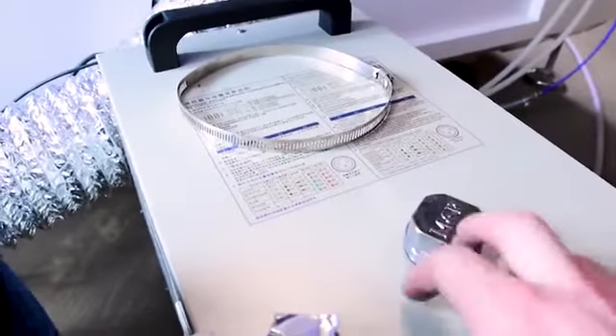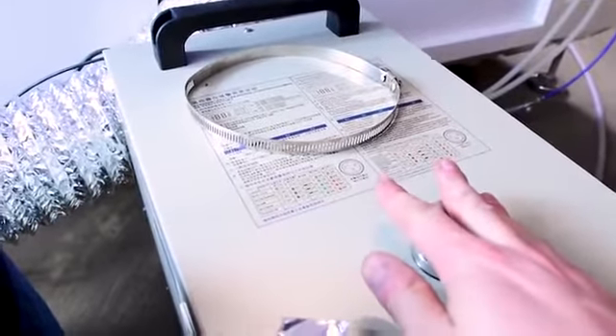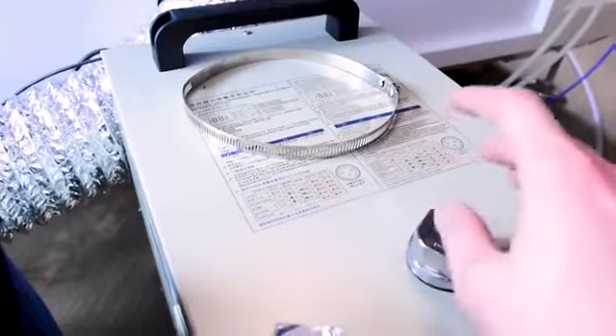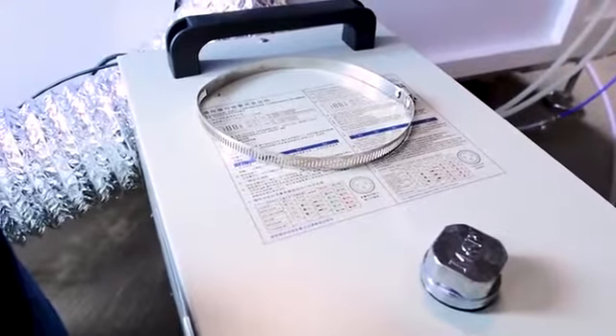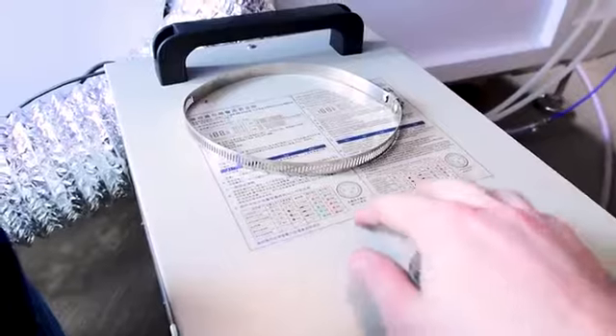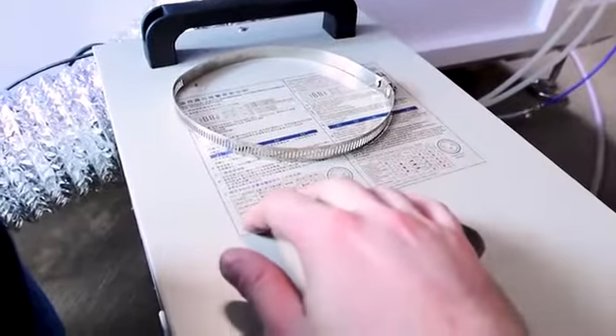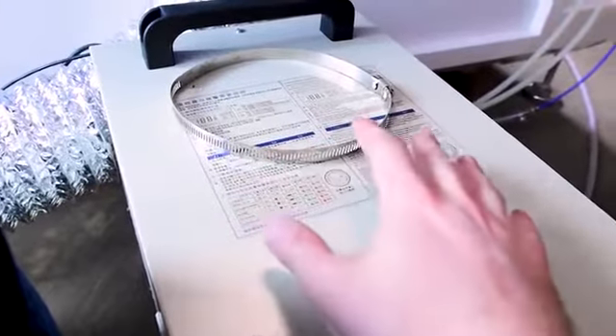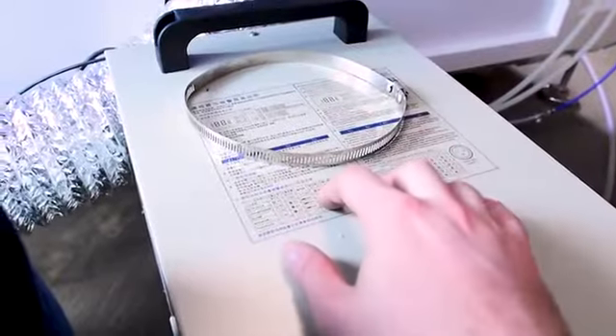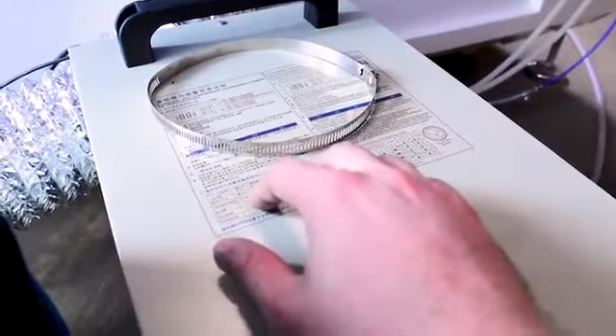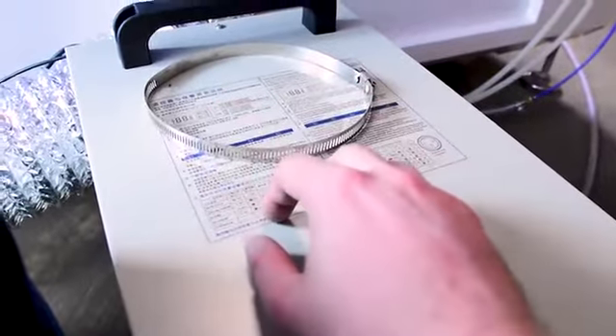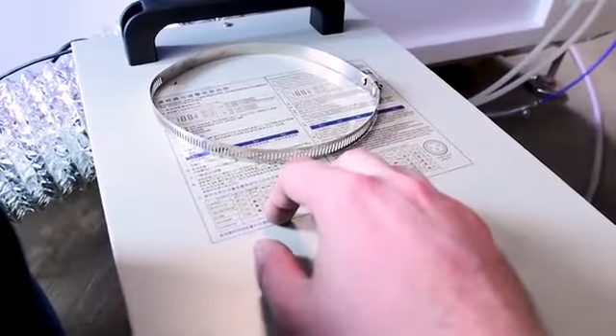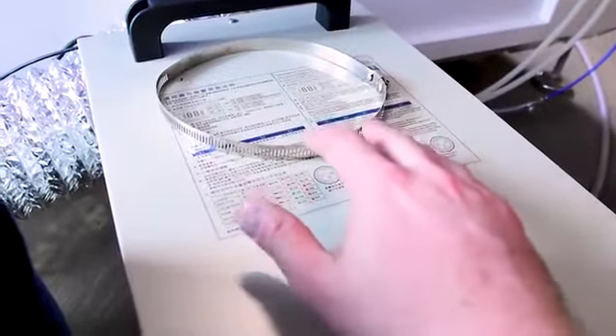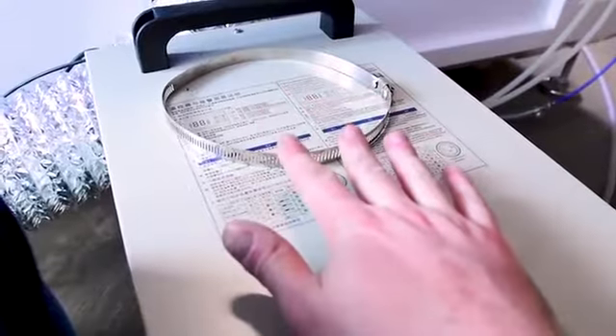I actually bought 2 of these chillers, one for the CNC router and one for the laser. These are really nice. They're refrigerated. They're not just relying on a radiator to cool the tube. With a tube as powerful as I have, you must have a refrigerated chiller. But even on the 40 watt, 50 watt, 60 watt tubes, I'd still recommend a refrigerated chiller. It makes a huge difference when your laser tube is running at a consistent temperature. The power output is nice and even, and the lifespan is greatly enhanced.